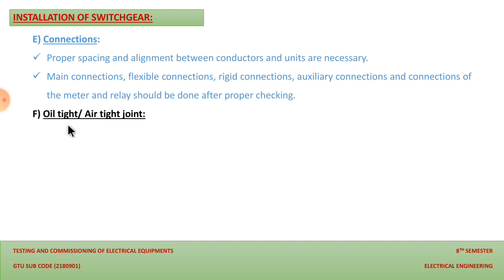And the next point is oil tight and air tight joints. So basically we provide proper insulation, so that there is no leakage of the oil in future, and also air should not enter inside the machine or switchgear. So yes, proper gasketing and a proper rubber gasket is provided for the fittings of such switchgear, because leakage will become harmful for the future operation.